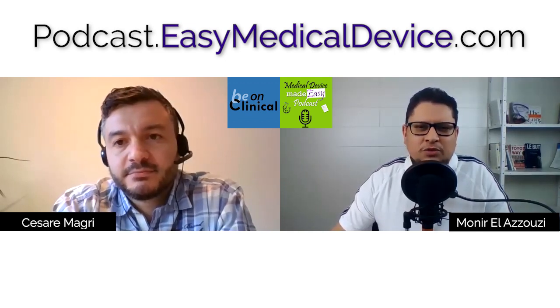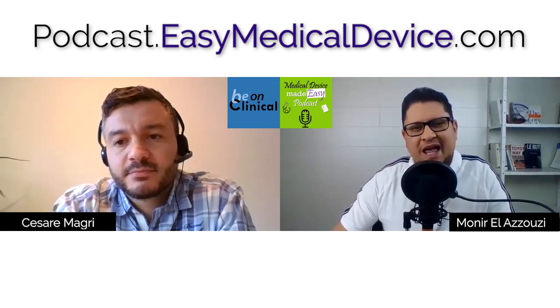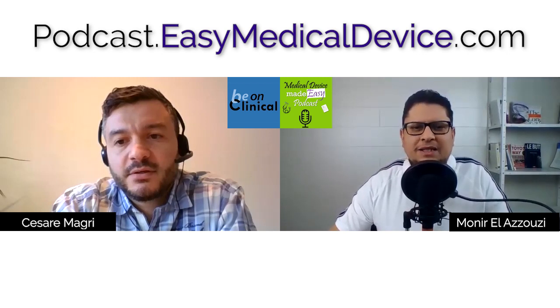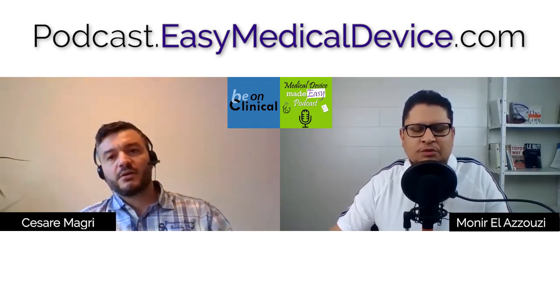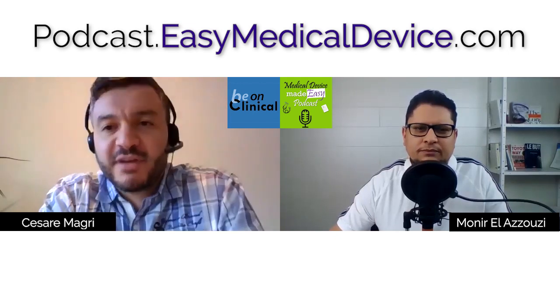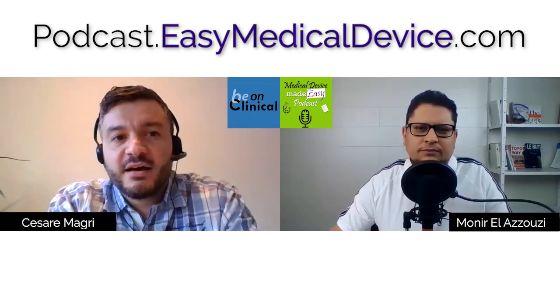So Cesare, I wanted you to really help the audience first understand intended purpose. Do we have a definition or something that exists that can make it clear for people what is intended purpose? So I like to define the intended purpose as the description of the medical problem that you want to address with your medical device.